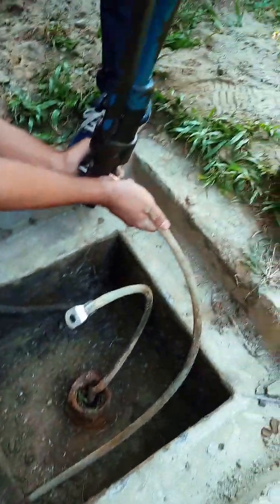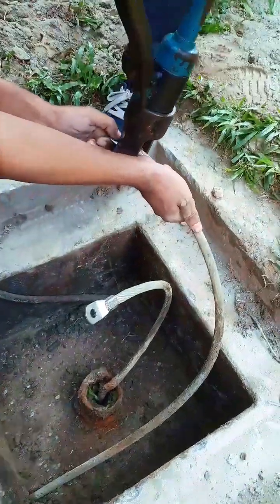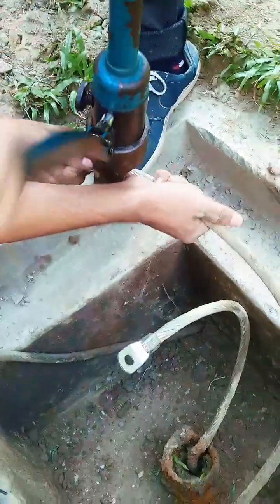Importance of regular earthing maintenance. Earthing pits should never be ignored. Even if the resistance value is good, humidity, soil movement, vibration, chemical reaction, and rust can slowly destroy the system. Lightning does not warn you. Fault current does not wait for your engineers. Your protection will only work if the path to ground is clean, strong, and reliable.